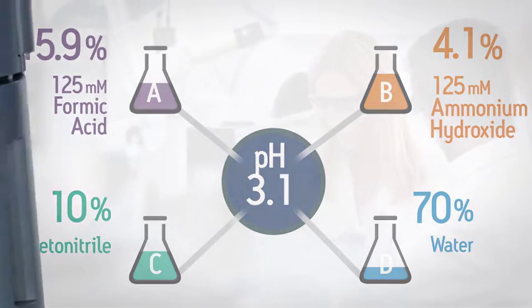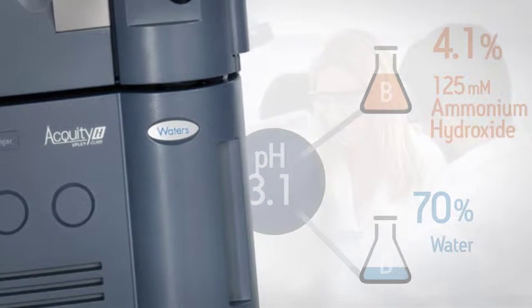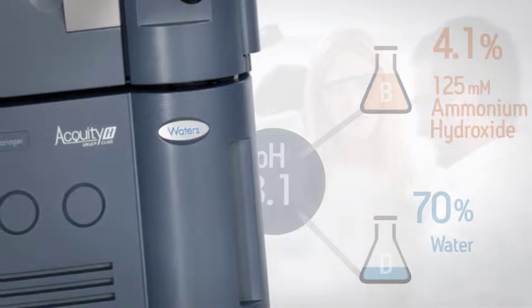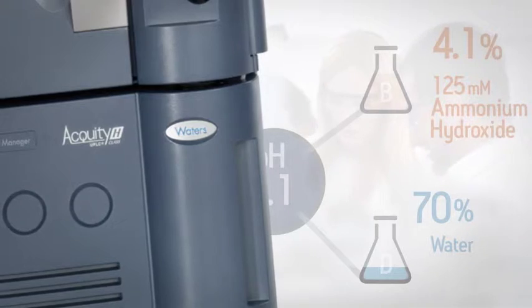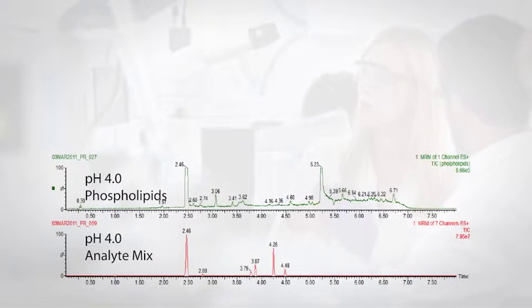So you can take the fullest advantage of your ACQUITY UPLC H-Class or H-Class Bio system. Auto Blend Plus can move peaks further apart for unequivocal identification. It can improve the reliability of quantitation by putting peaks on a flat baseline, and sometimes by putting the small peak first. Adjusting the pH can move analytes away from interferences.